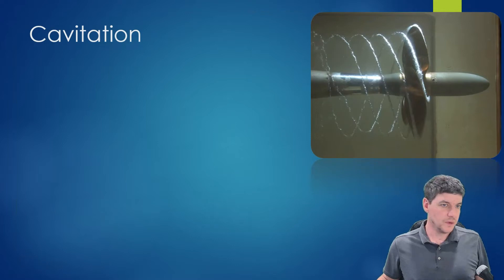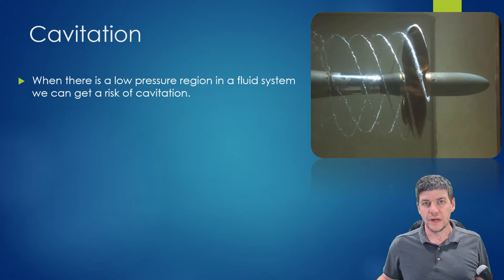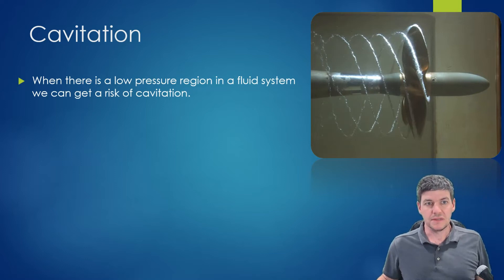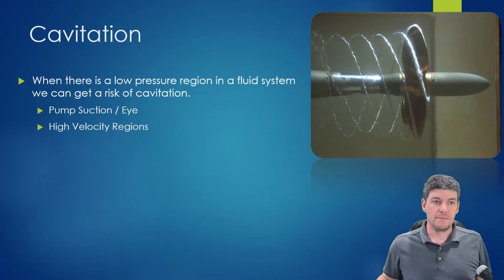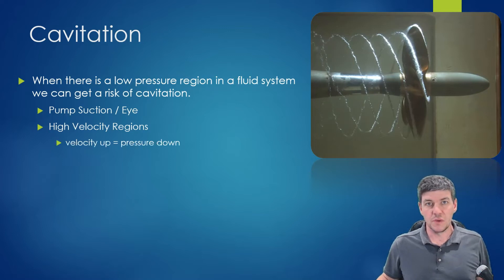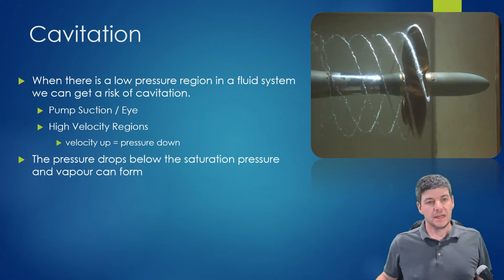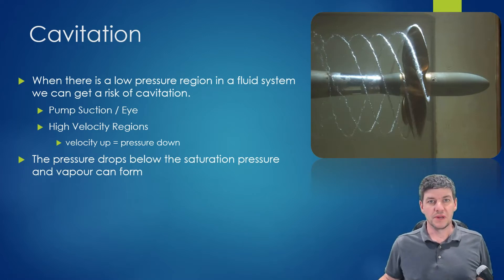Cavitation forms anywhere there is a very low pressure region where unexpected or unanticipated boiling occurs. In pumps, this happens on the suction side or right at the eye — the very center of the impeller — where pressures are lowest. High velocity regions also create low pressures, as described by Bernoulli's principle. Anytime pressure drops below the saturation pressure for the fluid's temperature, vapor can form, and that vapor causes cavitation.